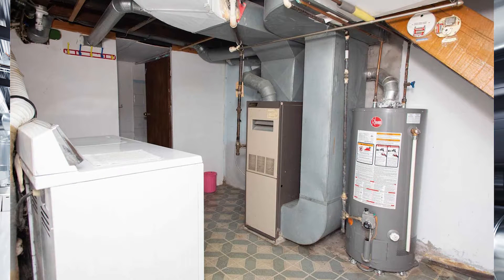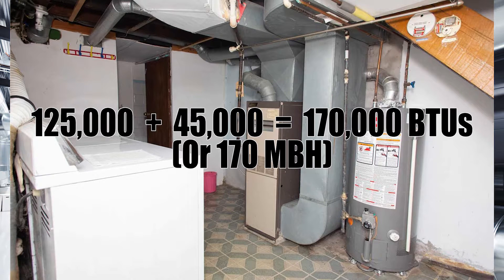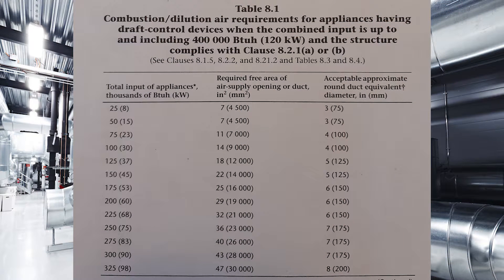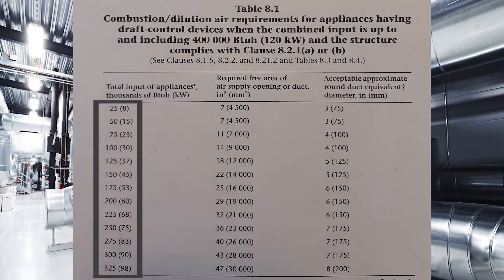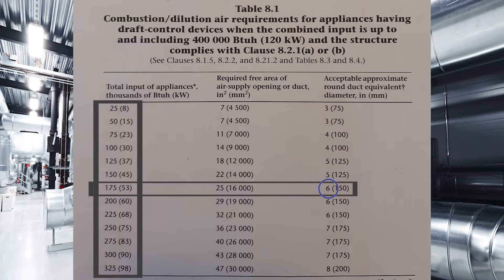For the next example I have two drafthood equipped appliances: a 125,000 BTU furnace and a 45,000 BTU hot water tank. First I add up the BTU loads: 125,000 plus 45,000 equals 170,000 BTUs. Because both appliances are equipped with drafthoods, I go back to table 8-1 and go down to 170,000 BTUs. It's not there, so I go to the next biggest — 175,000 BTUs — go across to the far right, and I need a 6-inch air supply.